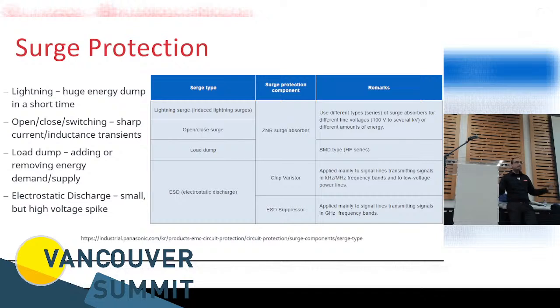And this isn't to say that just because you put in a surge suppressor, you're going to be protected, because even surge protectors come in ratings as to how much energy they can absorb, because they're sacrificial devices. And if the amount of energy coming down the line is more than the energy rating of this device, it will go up in flames, and so will the inverter. So you always want to make sure that whatever surge protective device you are putting in place is actually rated to handle the amount of energy you would expect to see come down that line.